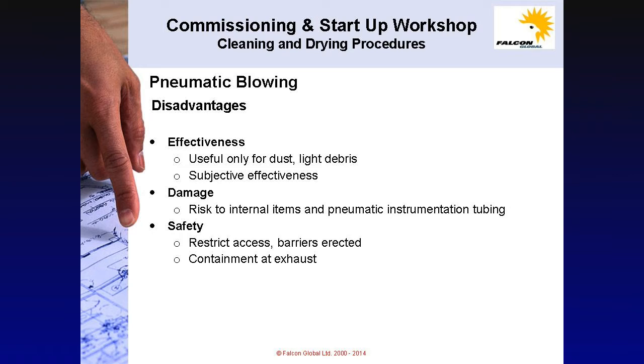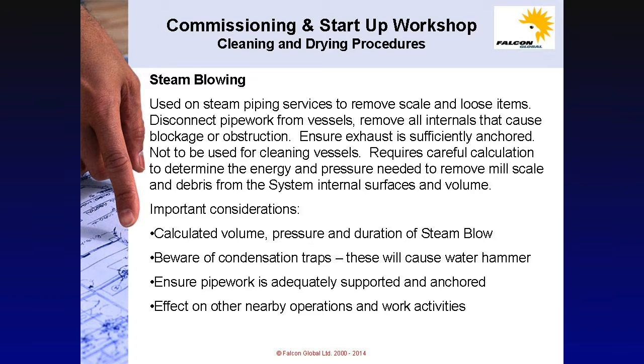With regard to effectiveness, this is highly subjective. It is only suitable to remove dust and light debris, and there is a risk of damage to any internals. Safety considerations are to erect barriers and restrict access. Steam blowing is used on steam piping services to remove scale and loose items. The normal procedure is to disconnect pipework from vessels and remove all internals that could cause blockage or obstruction. Ensure the exhaust is sufficiently anchored.